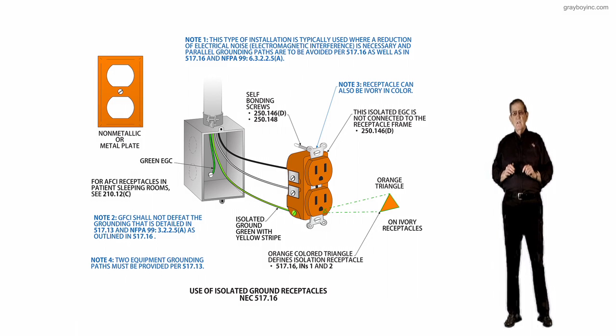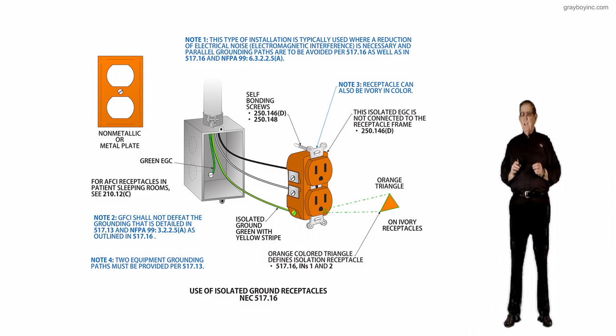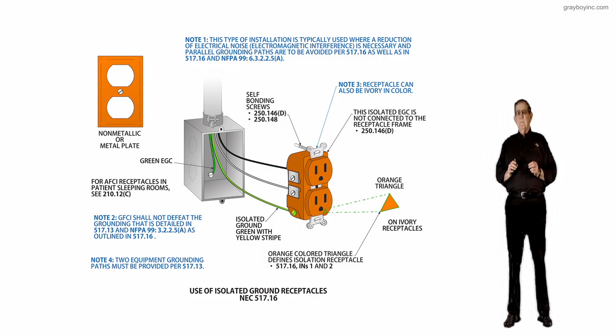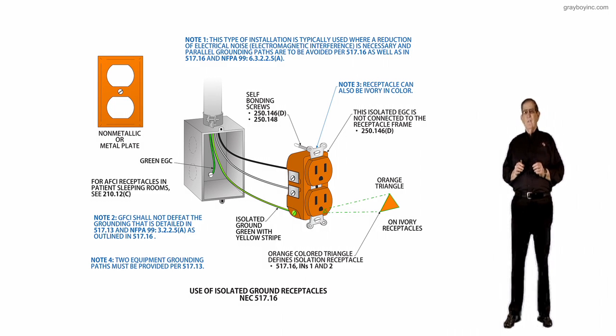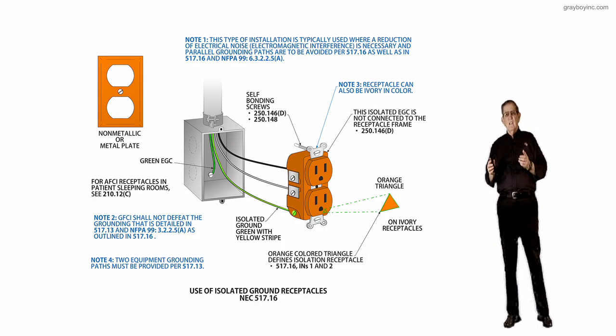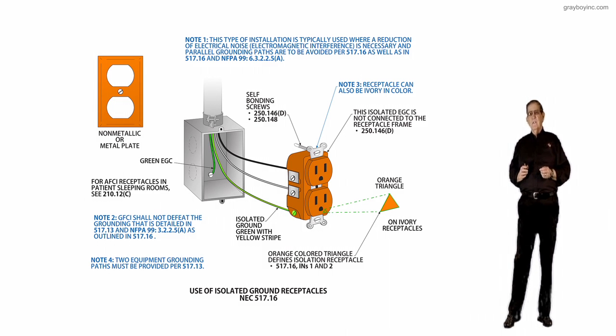The purpose of change was to accept a new sentence, which has been added to clarify the use of isolated receptacles outside the patient care area. It is the clear intent of this section that both grounding methods required in 517.13 be present in wiring methods used for isolated grounded receptacles. In addition, a separate equipment ground using a green insulated conductor, usually green with yellow stripes, identifies the isolation ground and shall be connected to the equipment grounding terminal of the isolated grounded receptacle terminal.